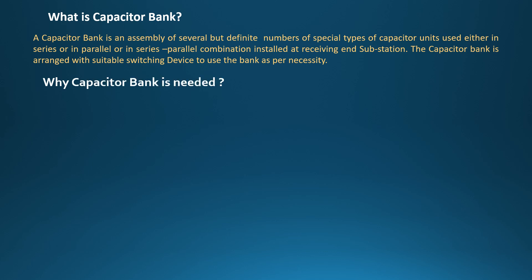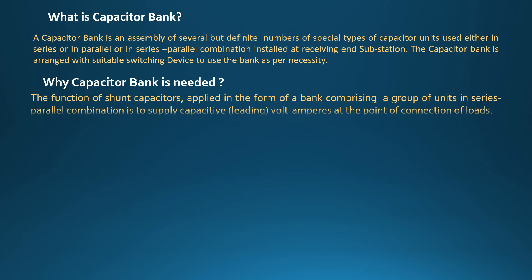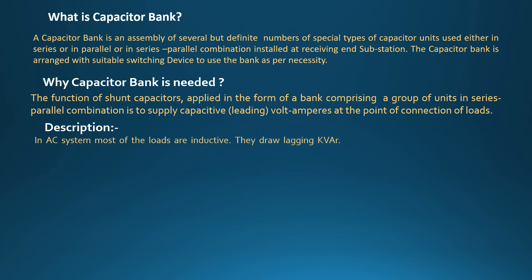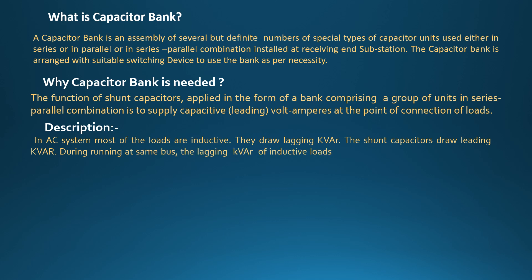Why is a capacitor bank needed? The function of shunt capacitors applied in the form of a bank comprising a group of units in series-parallel combination is to supply capacitive volt-amperes at the point of connection of loads. In an AC system, most of the loads are inductive — they draw lagging KVAR. The shunt capacitors draw leading KVAR. The lagging KVAR of inductive loads such as motors, welding machines, arc furnaces, etc., is compensated by the leading KVAR of shunt capacitors.